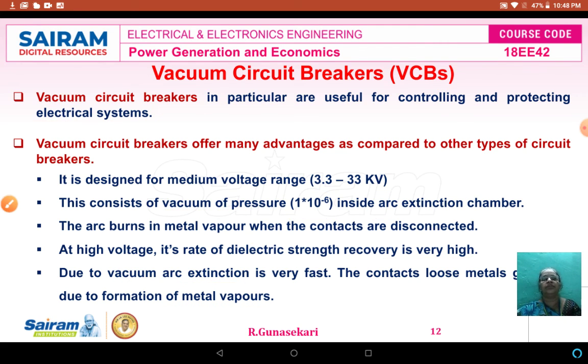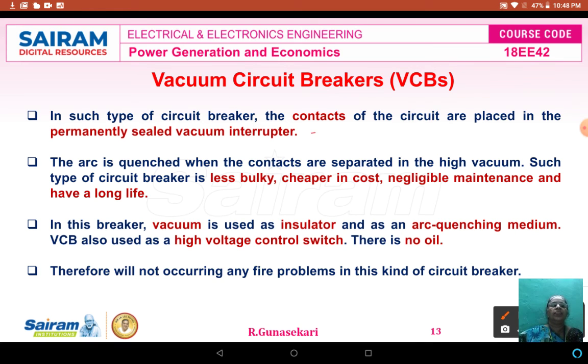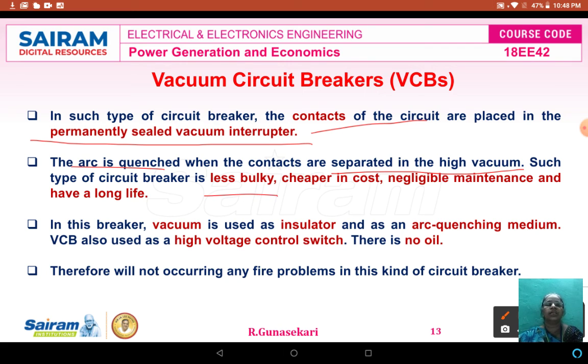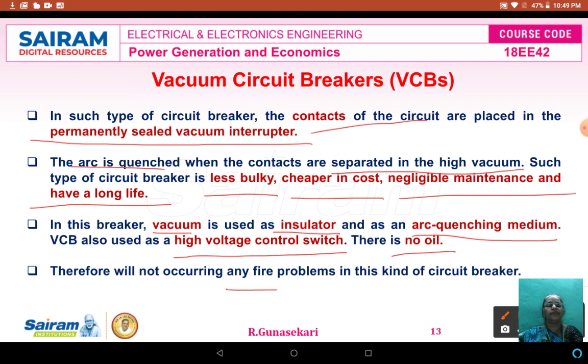Continuing vacuum circuit breaker: in this type of circuit breaker, the contacts are placed in a permanently sealed vacuum interrupter, and the arc is extinguished when the contacts are separated in high vacuum. The advantage of vacuum circuit breakers is that they are less bulky, cheaper in cost, require negligible maintenance, and have longer life. The vacuum is used as an insulator and as an arc extinction medium. No oil is used in the vacuum circuit breaker, therefore no fire problem occurs.